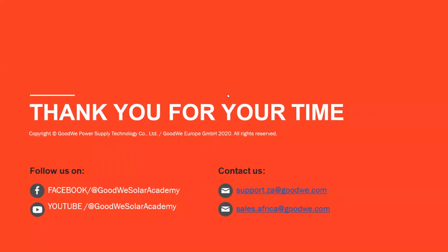Okay, David, a question for you, because it's definitely a more support-related topic. Have we managed to sort out issues with grid limiting on some smart meters? Yeah, so this is most pertinent on the Conlog meter. I think there's one or two other little meters that also have reverse feedback protection. So sometimes there is a leakage, even 5 or 10 watts, can cause these meters to trip off.